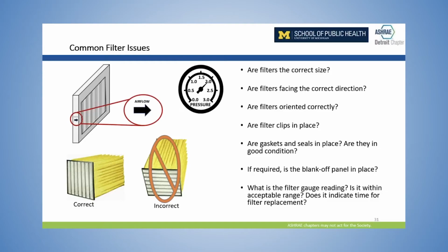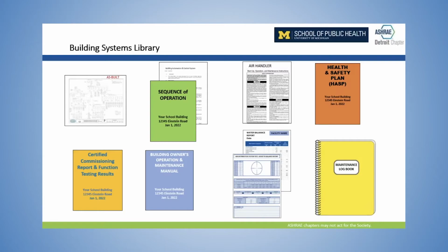Very briefly, I want to just talk about the building system library. Every building needs to have one. We should have as-built documents for our facilities that talk about how they operate, how they're intended to operate, and what the set points are, what the proper protocols and procedures are for startup and shutdown. And I'm going to rush through this because I've got just a couple minutes here.